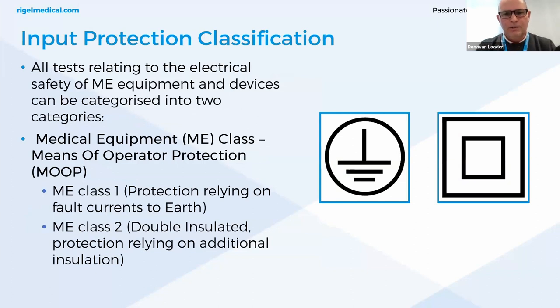For input protection classification, all tests relating to electrical safety can be categorized in two categories. Medical equipment class — means of operator protection (MOOP) — is class 1, earth-protected equipment, where protection is provided by insulation and protective earth connection. Or class 2 (MOOP 2), which is double insulated — protection provided by a double layer of insulation with no earth present. These icons are typically found on the rear of the instrument close to the power supply.